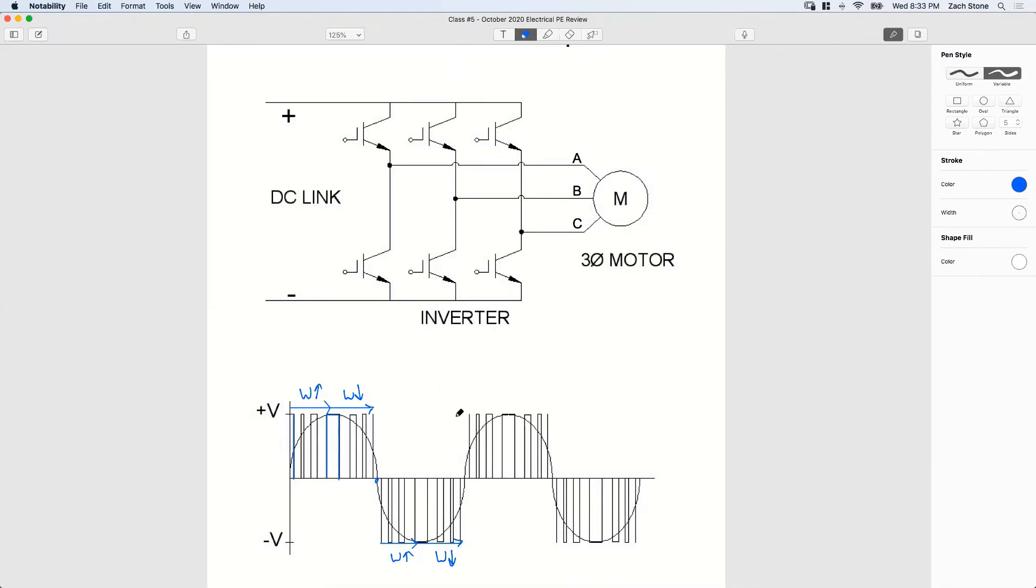So the motor is not getting a true sine wave. But guess what? Well, the average voltage of the pulse width modulated output will equal the sine wave. And since the widths are varying, but biggest at the peak and back down, you're still going to create stator poles to get that motor spinning.